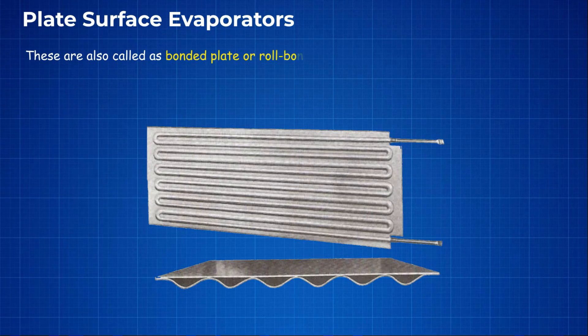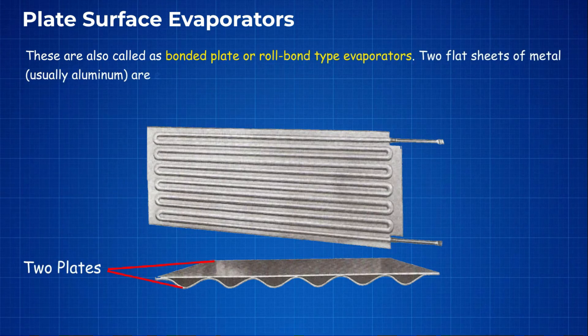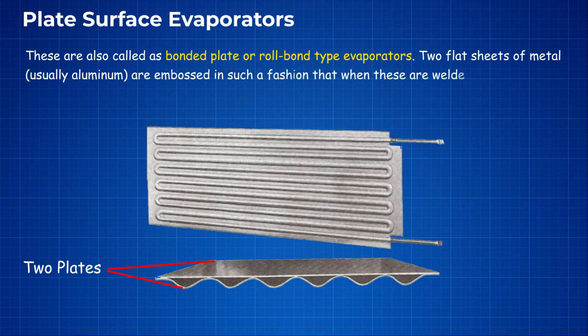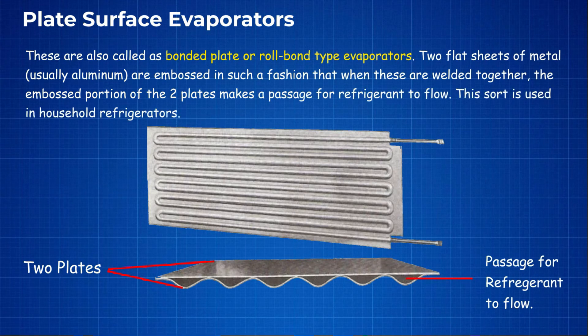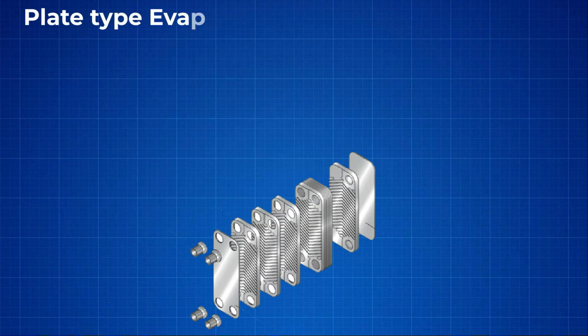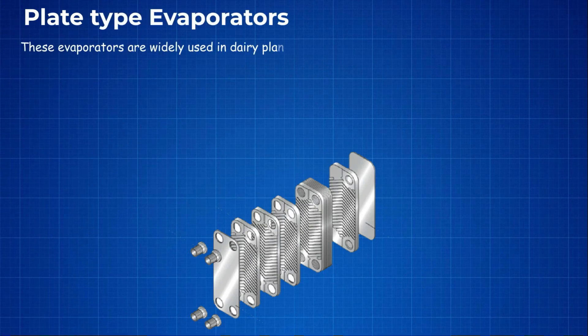Plate surface evaporators, also called bonded plates or roll bond type evaporators, consist of two flat sheets of metal, usually aluminum, embossed in such a fashion that when these are welded together, the embossed portion of the two plates makes a passage for refrigerant to flow. This type is used in household refrigerators.